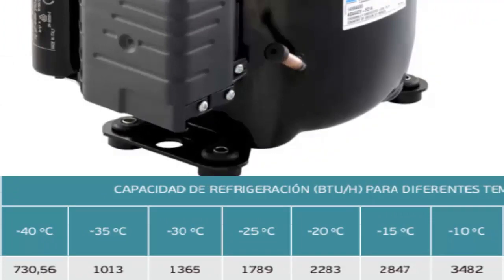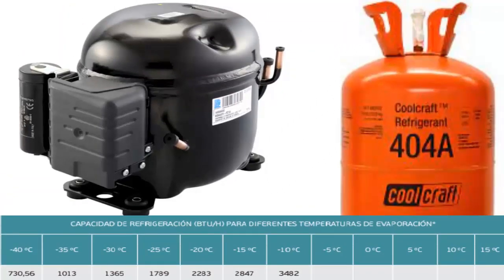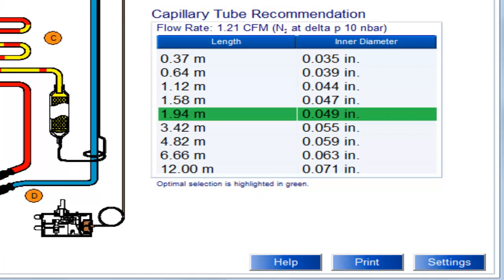At a temperature of minus 10 degrees Celsius, the cooling capacity of the half-HP compressor is 3482 BTUs per hour. We are displaying the recommended capillary tube sizes for the half-HP compressor using 404A, with the most recommended size highlighted.